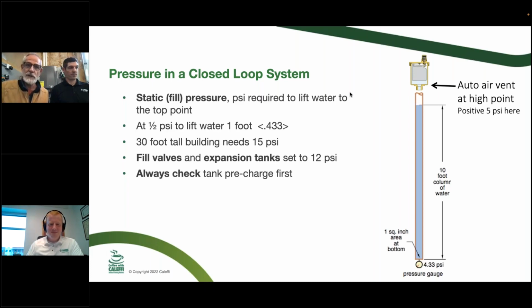The next pressure that we talk about is dynamic pressure. And that's the pressure when we fire up a circulator. If we had a gauge on the discharge of that circulator, it's going to add its delta P, its pressure differential, to move the fluid around through the loops. It overcomes the friction of the fittings, the pipe, the tubing, whatever might be in there. So static fill pressure, you check that with nothing running, you put that in, you decide what it needs to be. Dynamic pressure is what your pumps are going to add to the system. So anything, Cody, on that I put up?